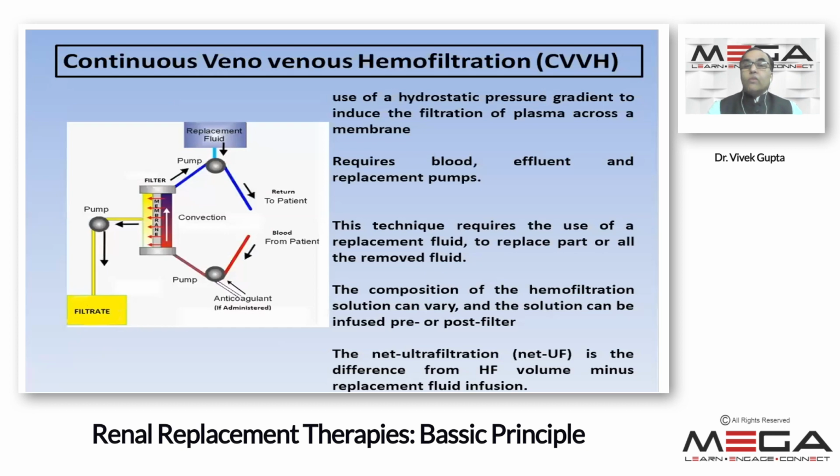The other is continuous veno-venous hemofiltration. Basically, as I said, it's a hydrostatic pressure gradient across the membrane from the blood side, so there is a solvent drag. It requires, again, the blood pump, the effluent pump, as well as the replacement pump. And here we need a replacement fluid. But please do not get confused: we are adding the fluid, and ultimately it is the ultrafiltration that we are targeting.